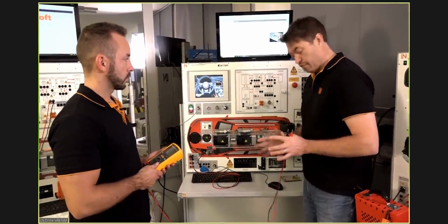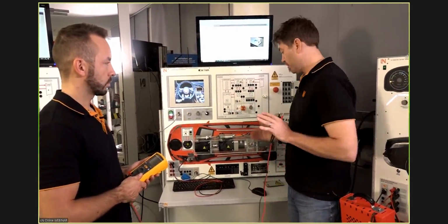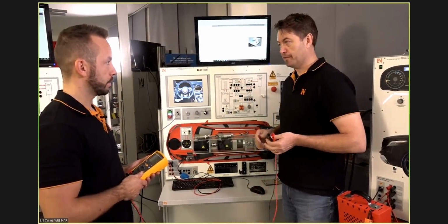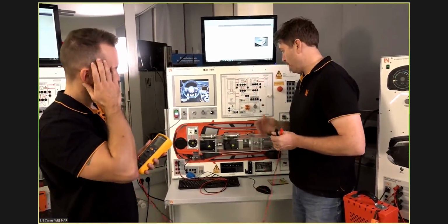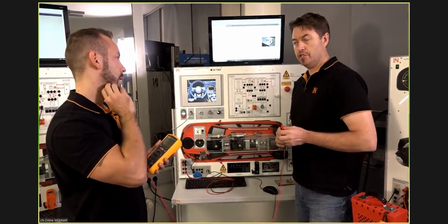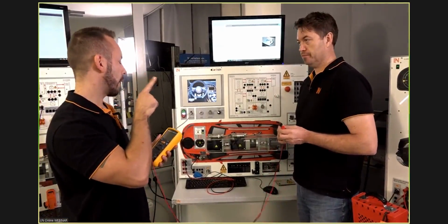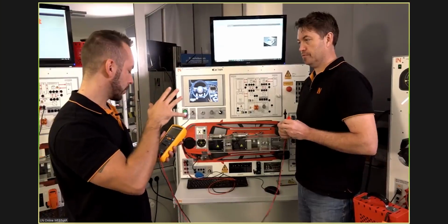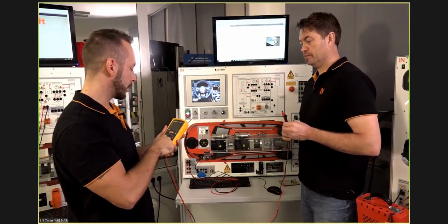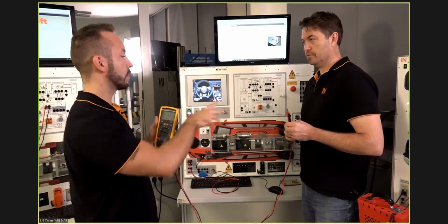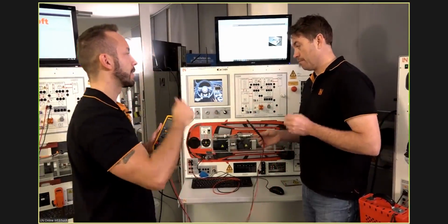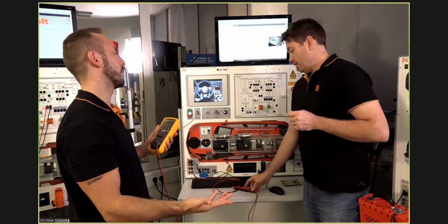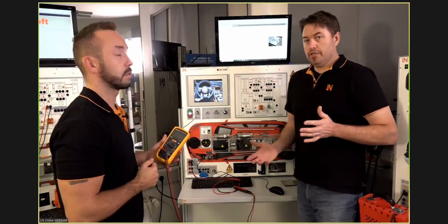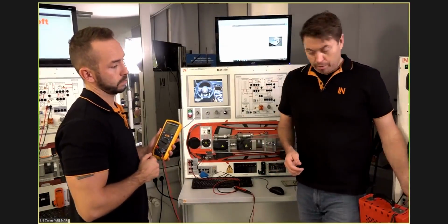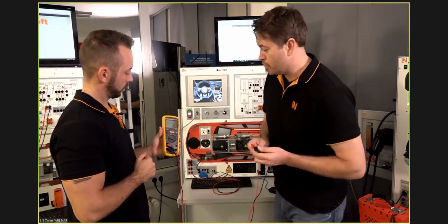Now the system is safe. I can now remove my gloves and work on things like the inverter, non-live high voltage. Yeah. But we now want to do an insulation test. What do you say to that? What I've heard before, there are different opinions on that. If you do an insulation test where we use high voltage, does it make sense to wear the gloves or not? It depends. It definitely makes sense to wear the high voltage gloves, because let's just do a little test.